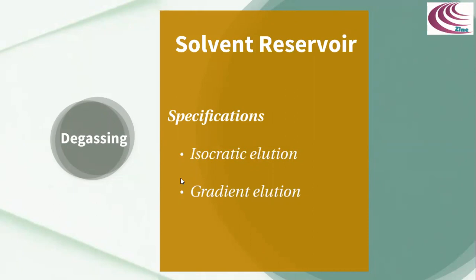So in order to elute a polar compound also within a reasonable time period, another mobile phase, which is polar in nature, is required for such samples. And when the elution is carried out by using two, sometimes more, mobile phases that differ significantly in polarity, it is termed gradient elution. The modern HPLC equipment has two or more reservoirs from which different solvents can be introduced into a chamber at rates which can be varied so as to adjust the polarity of the mobile phase.